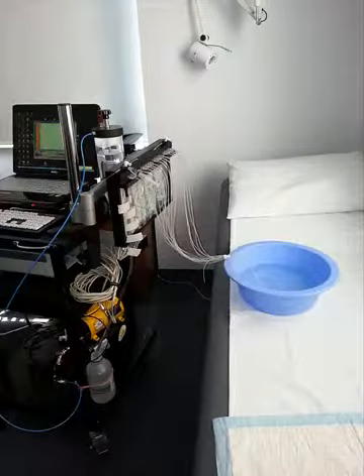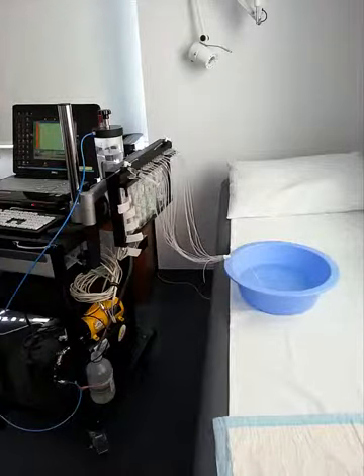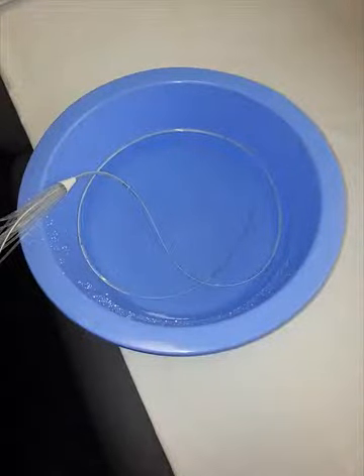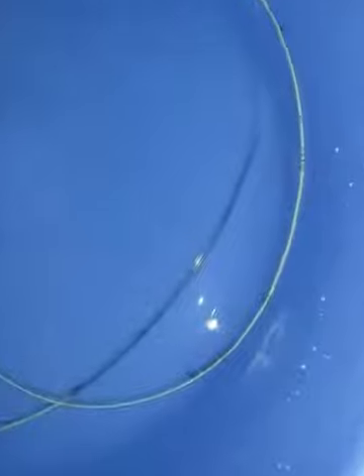You should now allow water to perfuse through the catheter. Place the catheter in a bowl of water with all of the perfusion ports on the catheter submerged. The bowl can be placed either on the patient's couch or on the manometry trolley. You will see small bubbles of air perfusing from the catheter. When these stop, all of the lumina of the catheter should be filled with water. You should let the catheter perfuse for another few minutes before using it, and perhaps give it a flush with some water using the technique described previously for clearing bubbles.